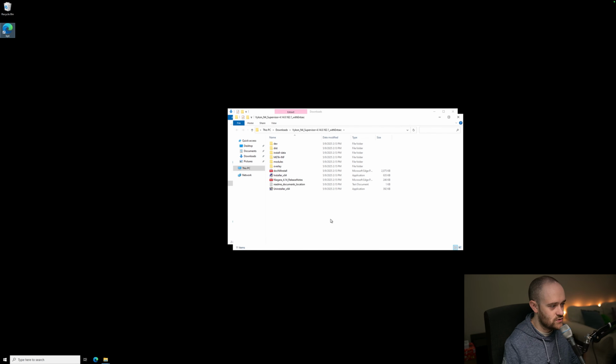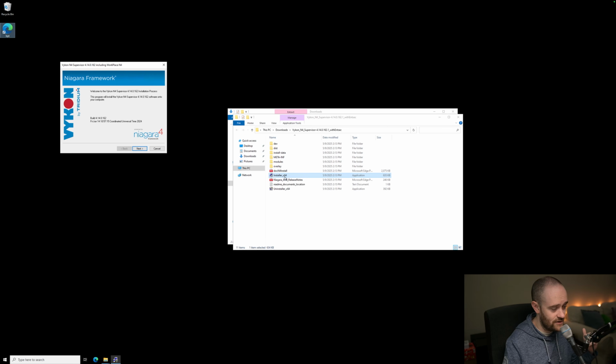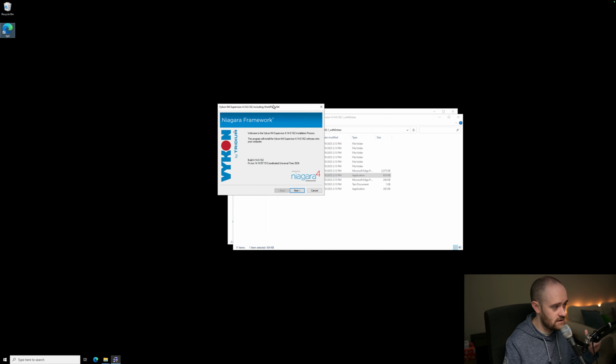All right, so we're extracted, and the thing we want to make note of here is that we have our installer x64. It used to be the case where Niagara could run on 32-bit and 64-bit versions of Windows. That's no longer the case, hasn't been the case for a little while now. So you'll only see the x64 installer. If you are using 32-bit and you go to install, it will yell at you and say that you're not using a compatible system. You'll need to upgrade or use a different computer for Niagara in order to actually have it run. So I know that we're on x64 here, so I'm going to hit the installer now.